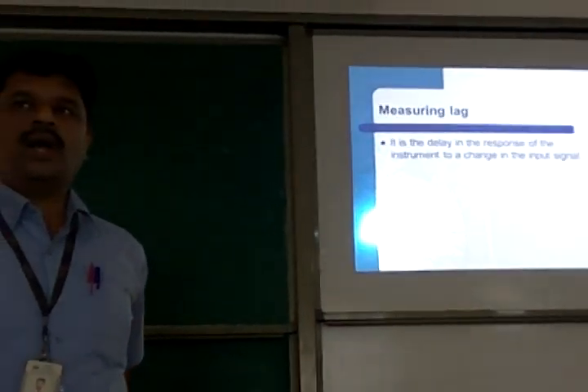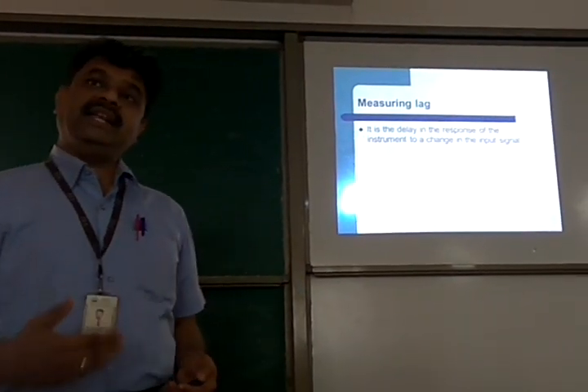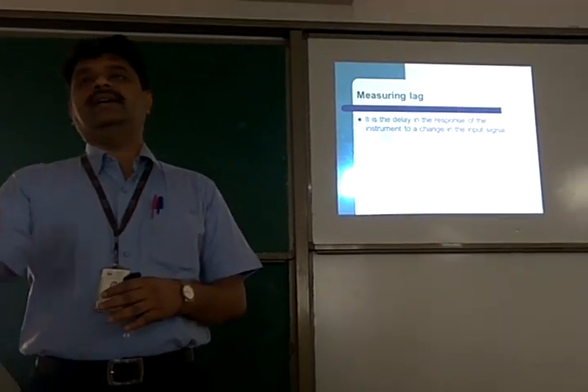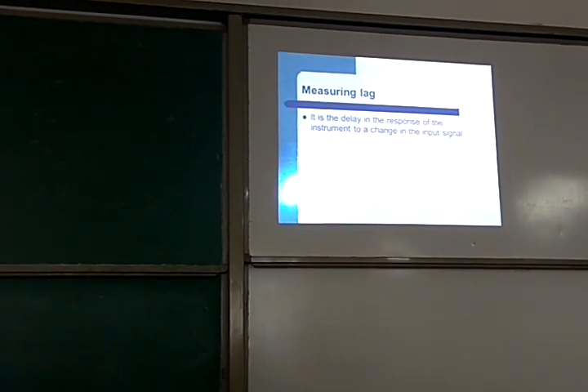Measuring lag is the delay in the response of the instrument to a change in the input signal. Response means the action by the instrument — once an input is presented, how much time it takes to show you the reading is the response time. For example, you take a thermometer and put it in a hot bath at, say, 70 degrees Celsius. The very next instant it will not show 70 degrees Celsius. The amount of time it takes to show the correct temperature is called measuring lag.